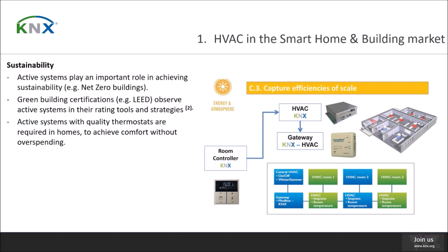Digging a bit more into sustainability, we can see that active systems play an important role in achieving sustainability. Good insulation is crucial, but a proper active system managing the HVAC is of the same importance. Green building certifications, as mentioned earlier, pay attention to the active systems too. The graphic shows a strategy from LEED training to pursue the LEED certification, capture efficiencies of scale, where room controllers and gateways help tremendously. For example, office buildings are not fully occupied at the moment. Many of us are working from home, and it's very easy with active systems like KNX to make sure only the right rooms are heated, etc. Not to mention that a proper thermostat is very important to achieve comfort.